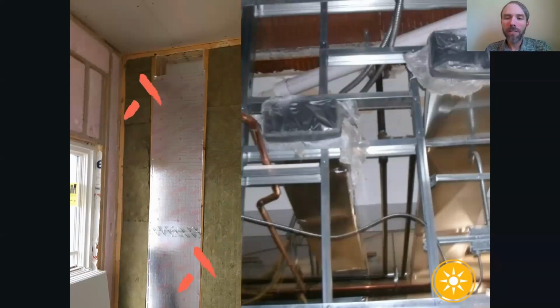Ductwork must also be properly sized using Manual D calculation, so improperly sized ducts may require they be updated or changed to match the new system and deliver air appropriately in the home. One solution could be to use your existing ductwork for your whole home ventilation system, which complies with the environmental quality ventilation section, which we'll get into in a little bit, and could be worth extra points for the enhanced ventilation credit. While not ideal, existing ductwork can be repurposed for your ventilation system, and you can seek an alternative way to deliver conditioned air to the home. Do note that LEED does not address asbestos in existing homes, but Enterprise Green and our Green Star program do. So before changing ductwork in older homes, check for and ensure asbestos is abated. That won't show up in your project checklist.